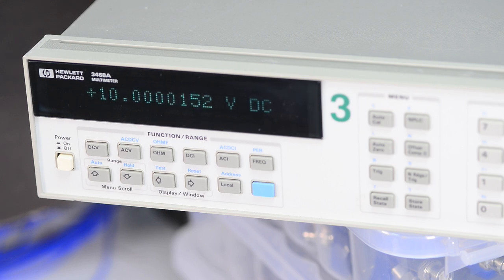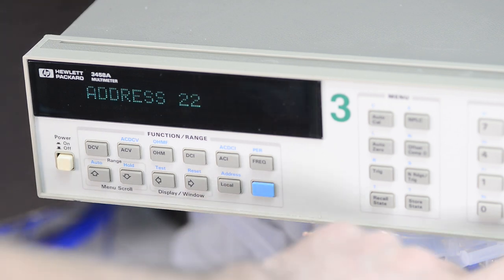It still seems to be working just fine, so I will connect the GPIB bus to it, and then we can run a long-term stability log with the external 10 volts connected, as well as monitor the calibration constants from frequent ACAL runs. So we can test if this A3 board is still drifting by 0.5 ppm per hour, or if the behavior has changed. I tested the GPIB interface, it's still working fine, as expected.